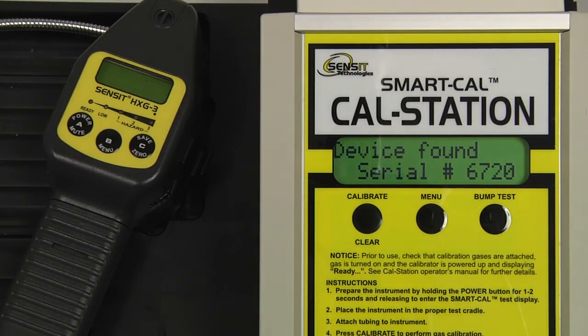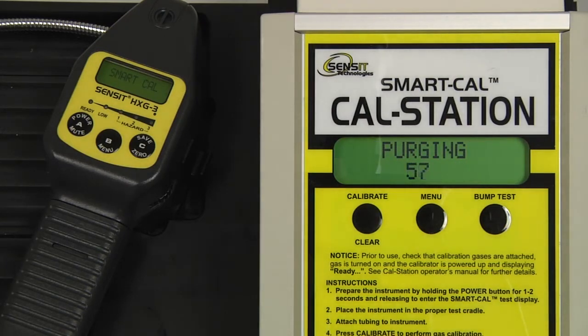Our device has been found. There will be a flow check, followed by a 60-second purge. After the purge is complete, the instrument will auto-zero, and the calibration will begin. We are now calibrating 2.5% methane.